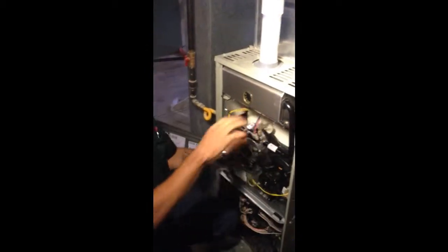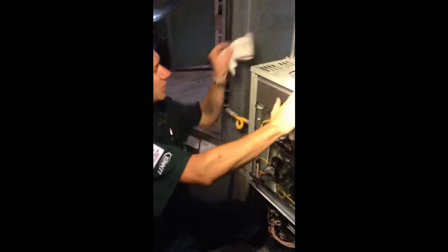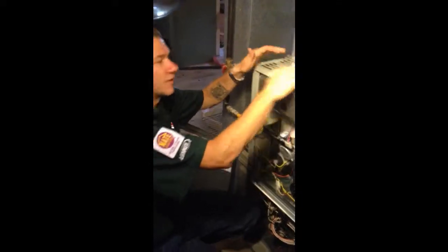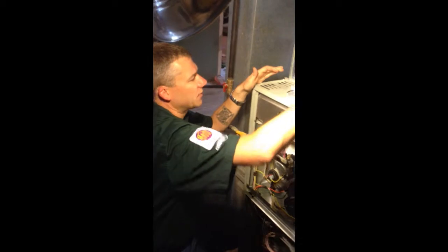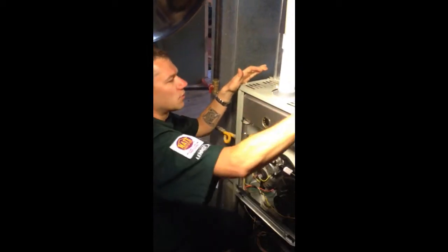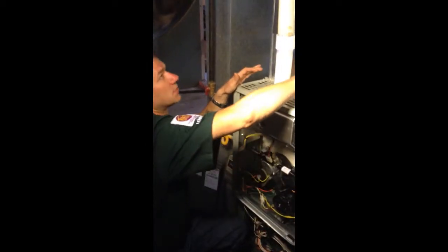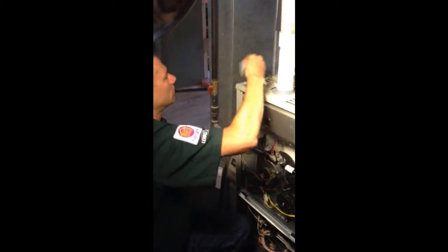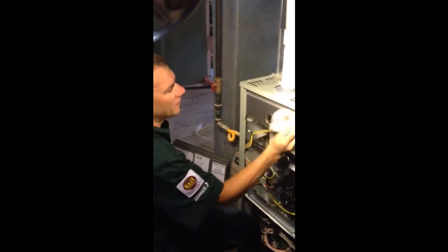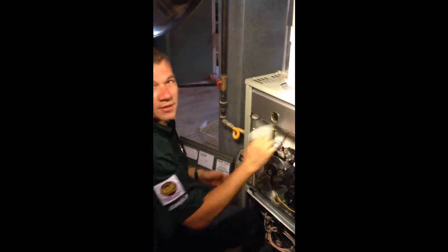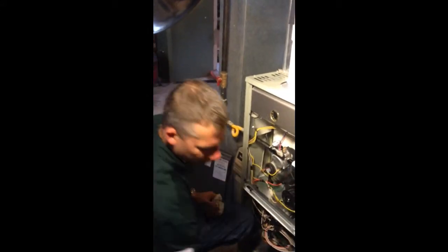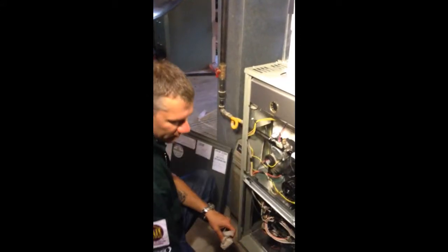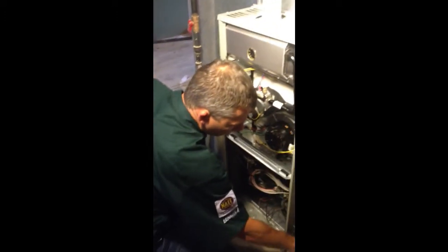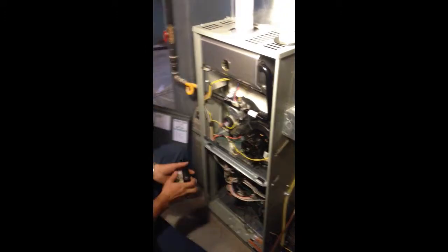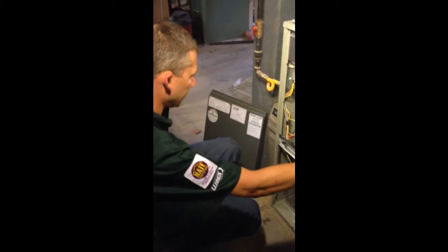So luckily, that rust I was worried about, it could just be on the outside, but there is some kind of a moisture issue down here. But there's no hole in it, so that's good. Great. So you said at 55 parts per million, you can start getting headaches. Yeah, if you're exposed to it for like 8 hours straight, you'll get headaches. And then Washington law says if it's 100 parts per million, then you have to red tag it. Right. But at that point, you don't want to be spewing carbon monoxide around your home.